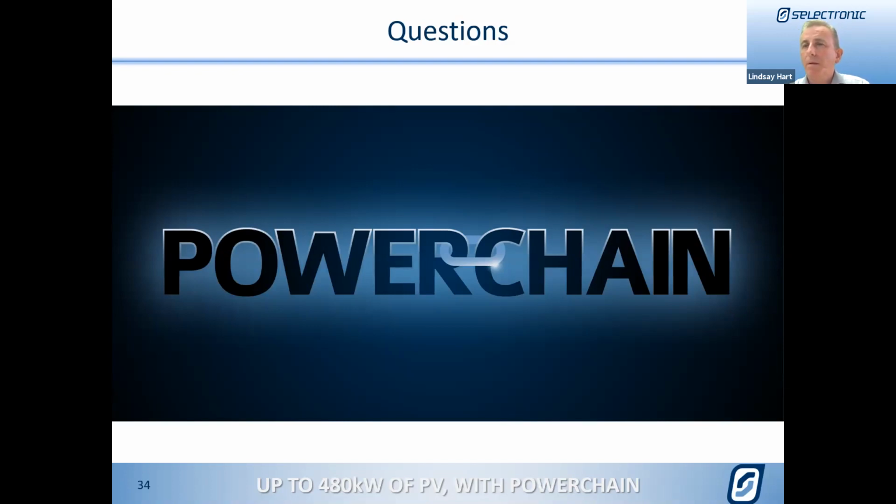So in terms of inaccuracies, one of the largest areas of problem we've had is with the shunts, and where people are using DC coupling and they haven't quite got the shunt right, or there's drift in the shunt and those sorts of things, and that can lead to inaccuracies in the state of charge. But no, in terms of the product itself, when set up and running correctly, no problem at all.